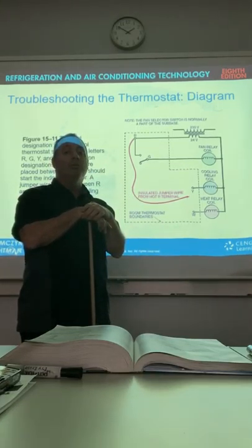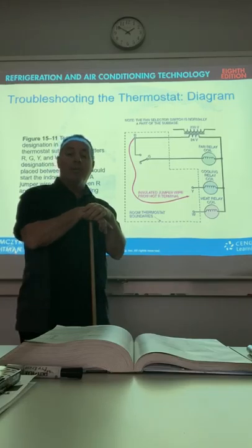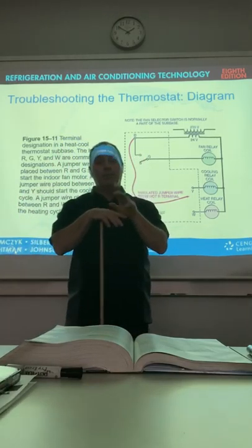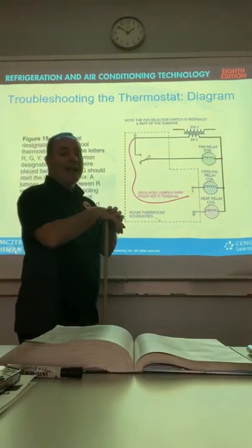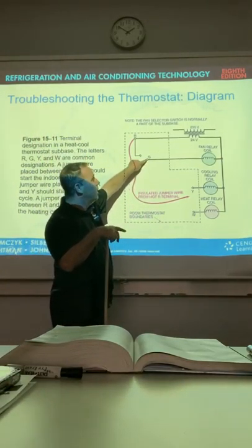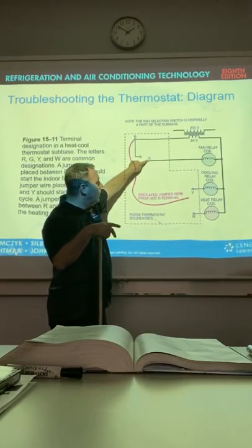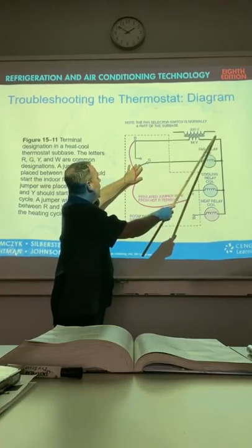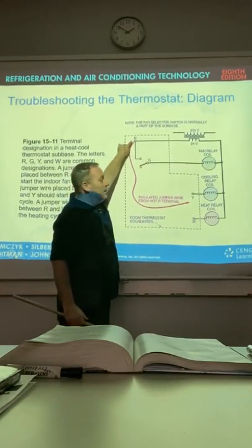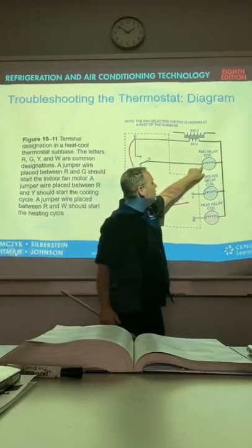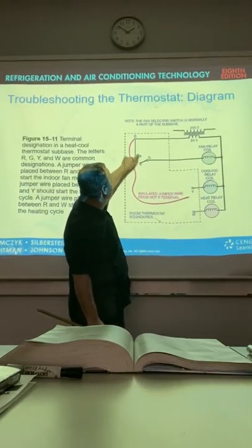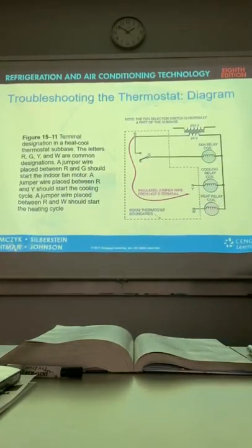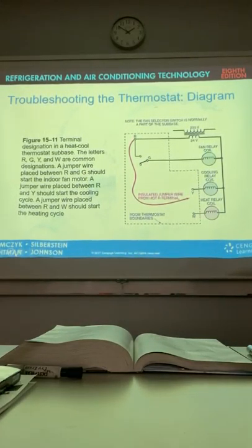I can take a jumper wire and connect it between R and G to see if that's going to come on. And I should listen for it to come on. I can take it and jump it out to Y and listen for Y to come on. Now, let's say I hook it to R to G and I don't hear a blower on. Well, I know I'm sending power to it, so now I'm going to go to where the indoor unit is and find out why it's not turned on. And right there at the thermostat wires to the unit, I should have power between R and common and G and common.